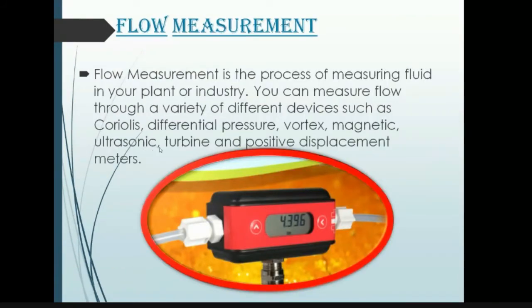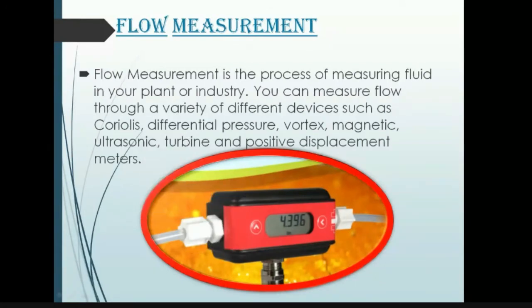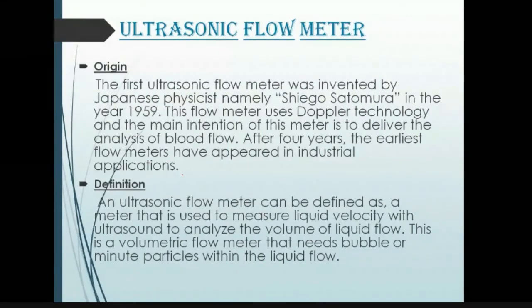So let's see what flow measurement basically is. Flow measurement is the process of measuring fluid flow in your plant or industry. You can measure flow through a variety of different devices such as Coriolis, differential pressure, vortex, magnetic, ultrasonic, turbine, and positive displacement meters. Basically, this topic has already been covered by group number 14, so I will not go through it. And now let's see the origin.